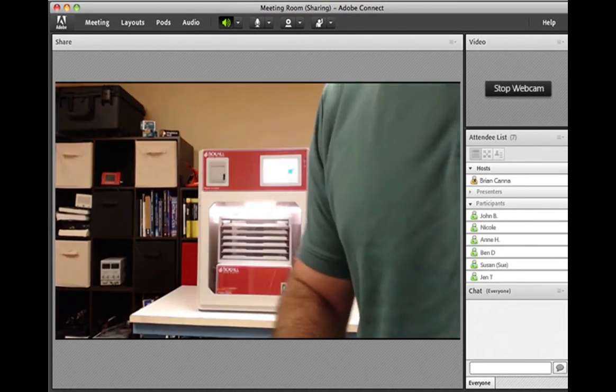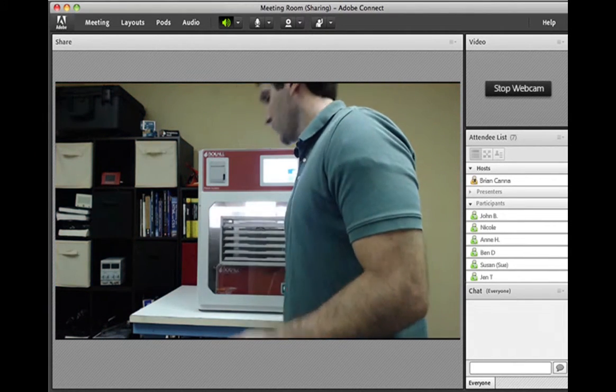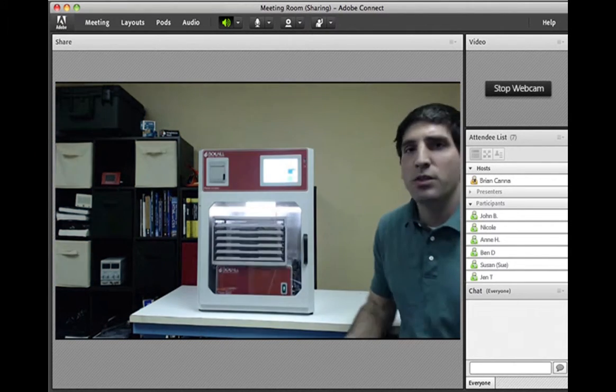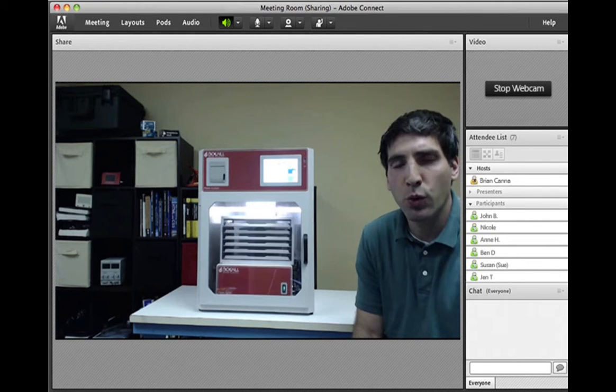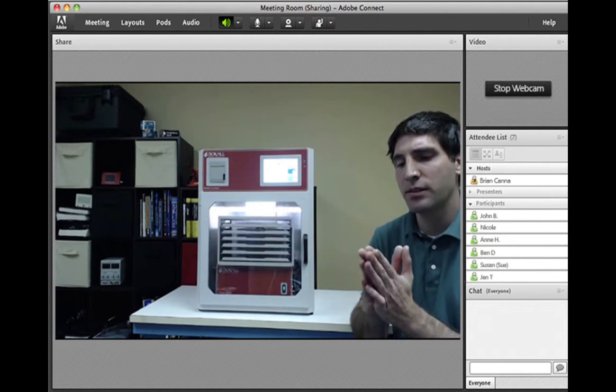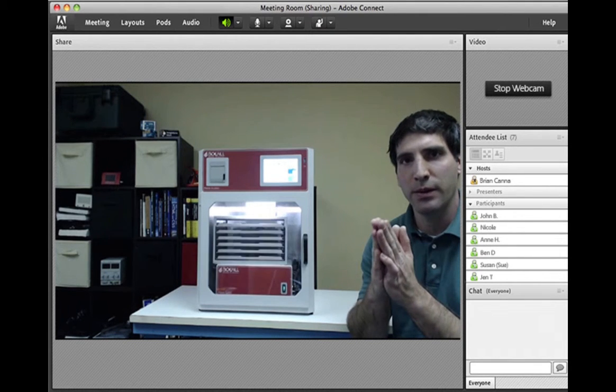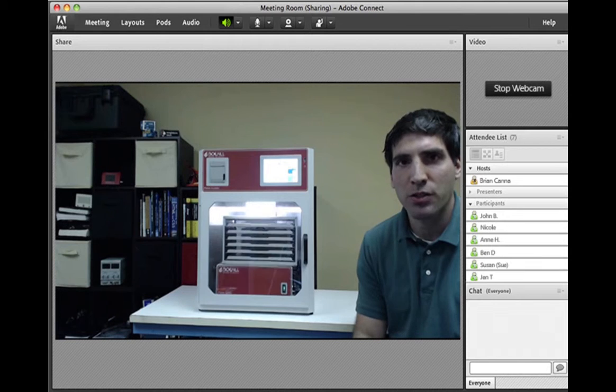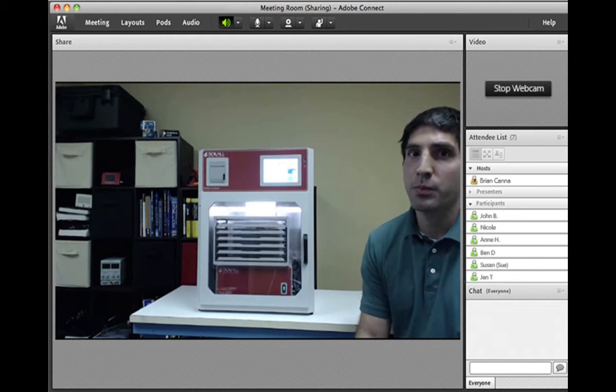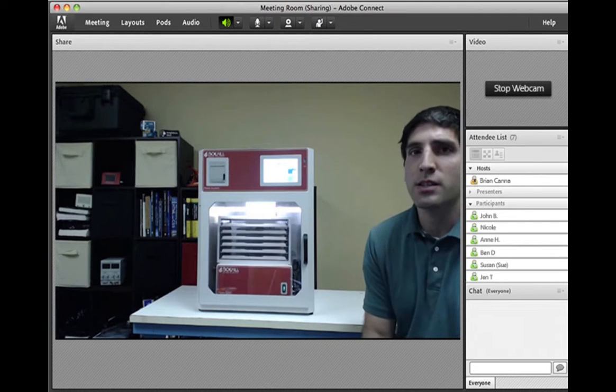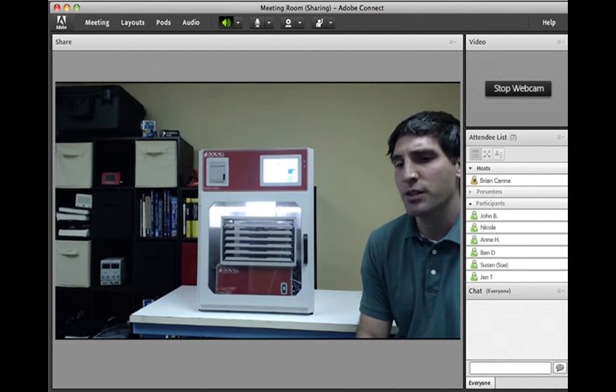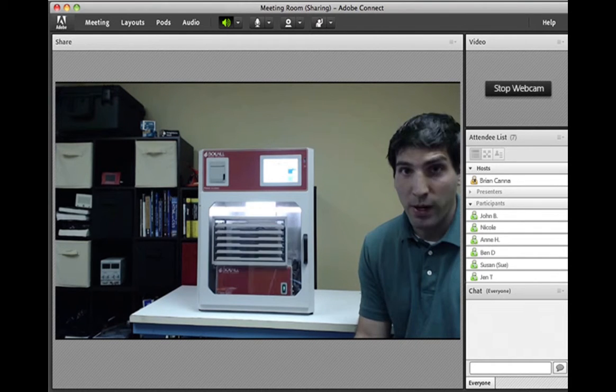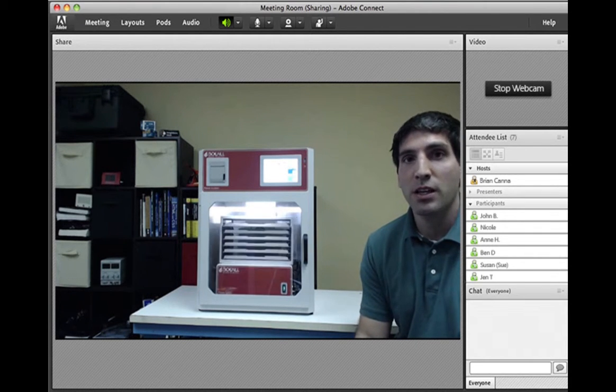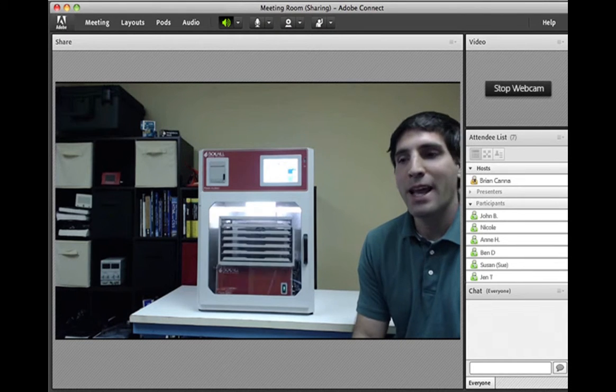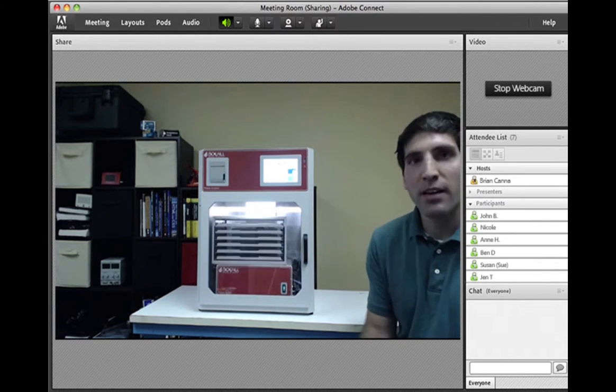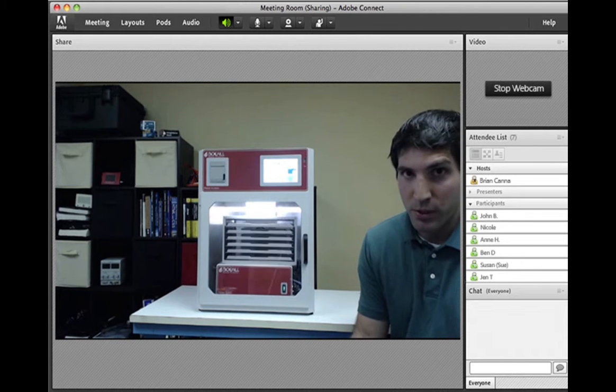So I said that the heating and cooling method was a little different than a standard unit out there on the market. This unit actually uses a Peltier heater cooler, and what a Peltier is, it has two different materials, and based on the way that you're passing electricity through those materials, they will either pull heat into the system or suck heat out of the system, unlike a compressor. Now a compressor actually works with refrigerant, and what happens is you're using electricity to compress a gas. When that gas expands, it sucks energy out of the surrounding atmosphere, therefore lowering the temperature.